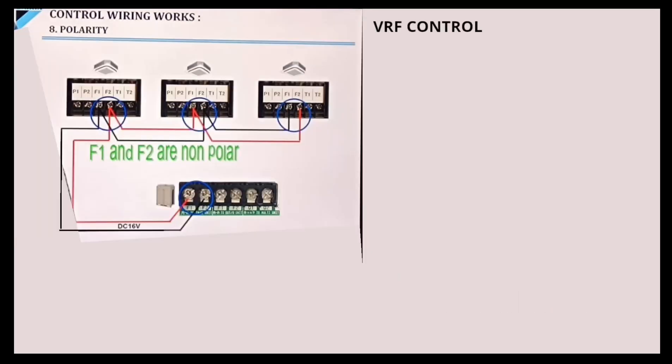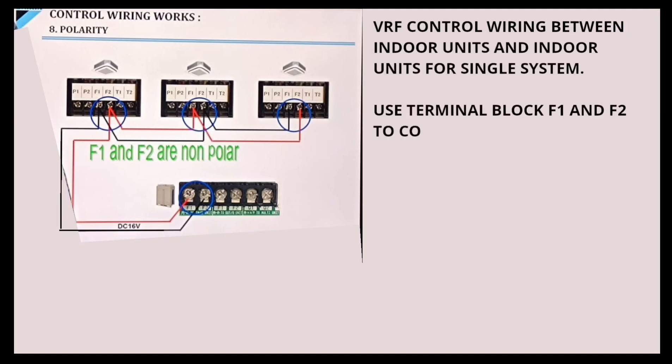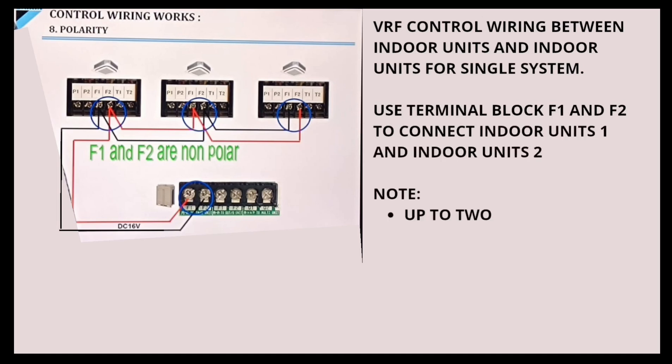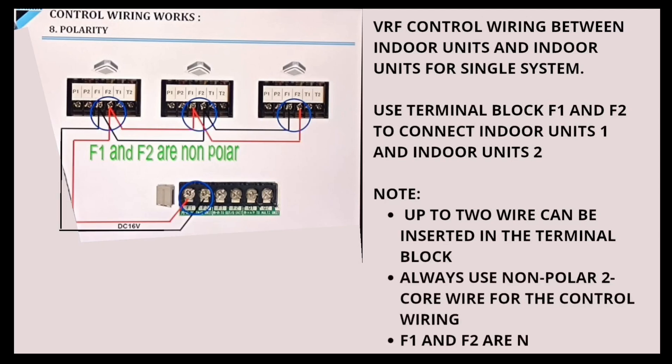VRF control wiring between Indoor Units and Indoor Units for a single system. Use Terminal Block F1 and F2 to connect Indoor Unit 1 and Indoor Unit 2. Note: up to two wires can be inserted in the terminal block. Always use non-polar two-core wire for the control wiring. F1 and F2 are non-polar.